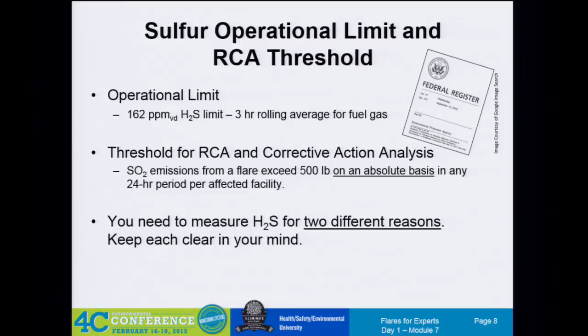For the H2S analyzer, on that low span to comply with the 162 ppm, there's a span requirement of 300 ppm. That's pretty typical, that's what you had for J, and typical of what's in the consent decrees, or around 320 sometimes, for a nice annoying reason, for facilities that now have a consent decree saying span to 320 and a rule that says 300. So they're going to have fun with that.